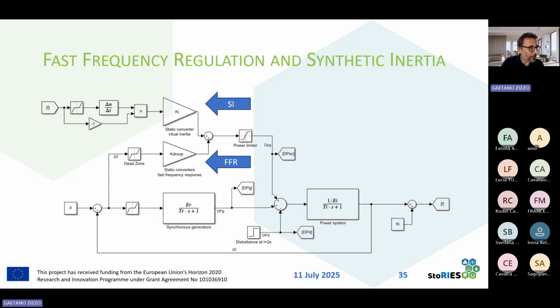A few years ago, I participated in the writing of a proposal for a European research project in which we suggested installing battery storage systems in sites where carbon power plants were installed, for replacing their contribution to frequency regulation and to the inertia. That was very interesting because replacing the traditional system with batteries, respecting the same locations, allowed us to not modify the grid that was already adequate for carrying the power that should have been delivered by the batteries.